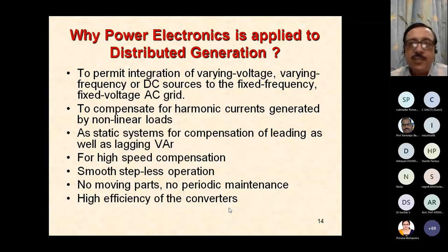Our semiconductor devices do not operate with more than about 125 to 150 degrees centigrade at the junction point inside the semiconductor. So if you're talking about the case of the semiconductor, not more than 100 degrees centigrade at all. So you have to control the temperature of the devices to maintain their operation so that they don't fail. And at the same time, you have to control the losses in the system so that you get the highest efficiency.